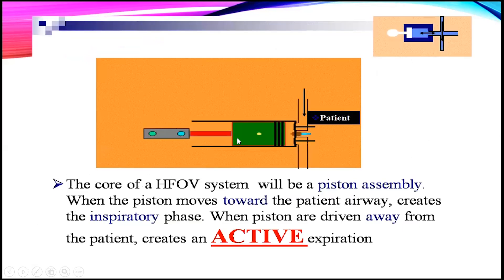The core of the HFOV system is the piston assembly. The airway flow entering the patient is connected to a piston. When this piston moves in and out of the airway, it pushes air into the airways and pulls air out, producing active inspiration and active exhalation. The piston moves very rapidly, creating oscillation around the mean airway pressure, creating active inspiration and active expiration. This active expiration allows for very high rates of piston movement.